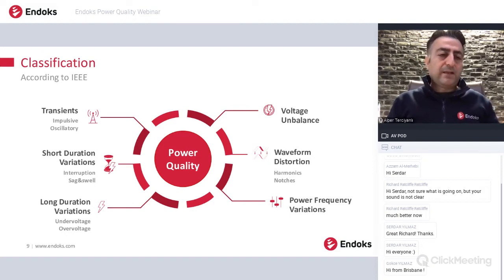There is also another definition: the short duration variations, meaning interruptions, sags and swells. Interruption is when there is no supply. Sag and swell, I think, are the most common power quality problems we observe on many systems. Sags and swells occur because of the sudden switching of some loads, like capacitor switching, heavy loads like motors, or energizing transformers. These sags and swells are seen on the system from milliseconds up to 3 seconds.